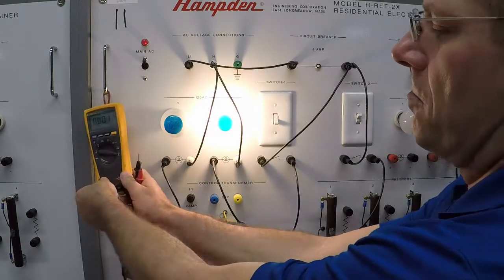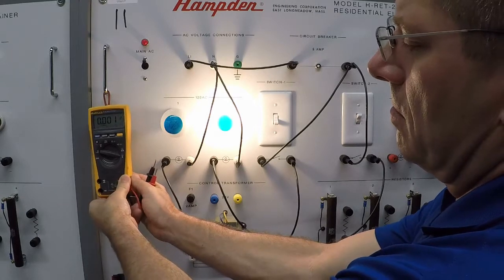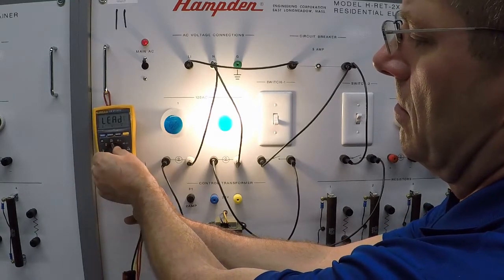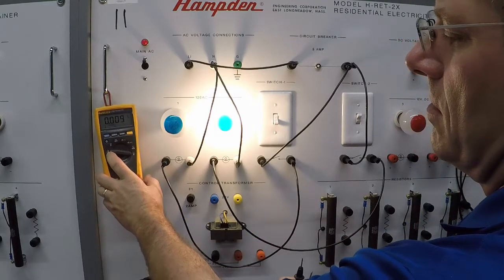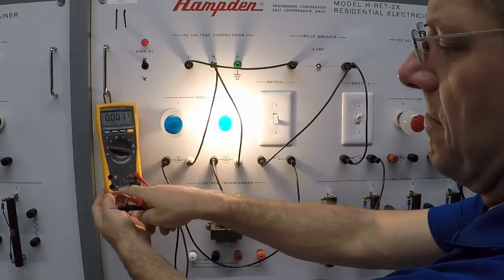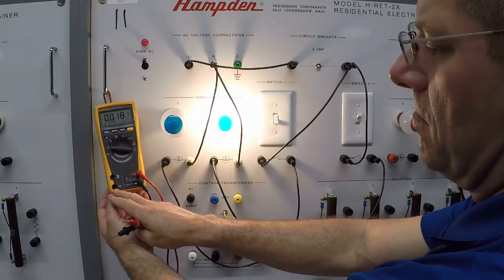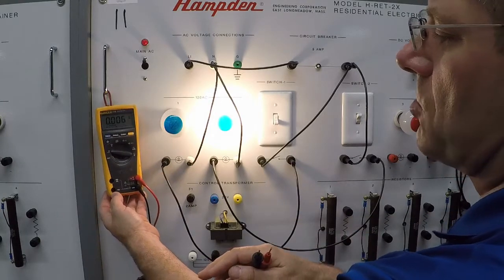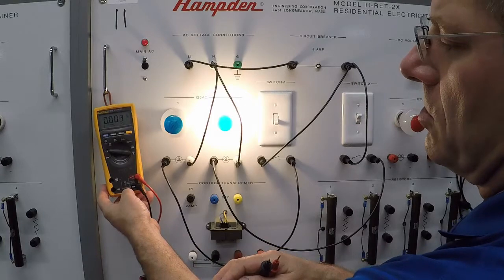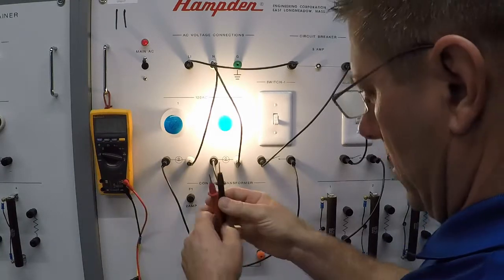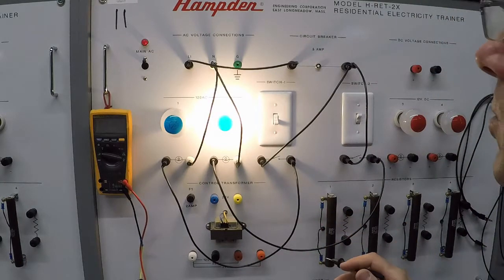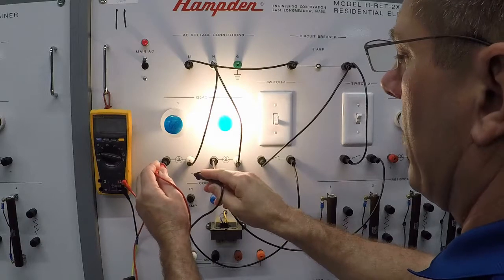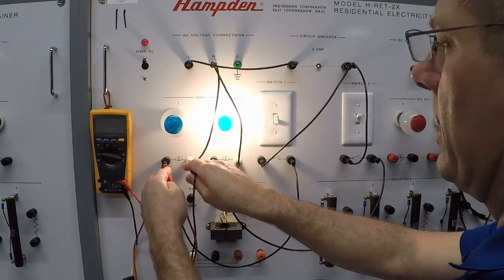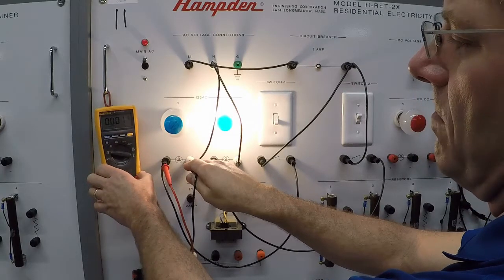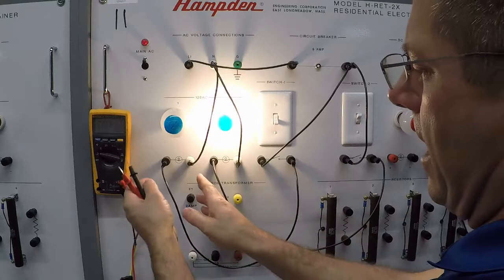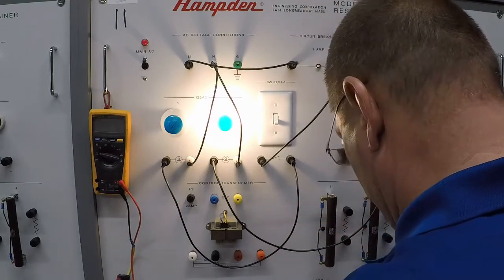We've got to place our meter back to the voltage position for the probe connection. Set the meter back to voltage. Can't stress enough that you always have to verify that you've removed from the amp measurement and placed it to the voltage resistance measurement, and place the meter in the voltage measurement position as well when you're placing the probes in parallel with a load. So our measured EL1 at step 13 is 0 volts. So we do not have voltage applied to light bulb 1.